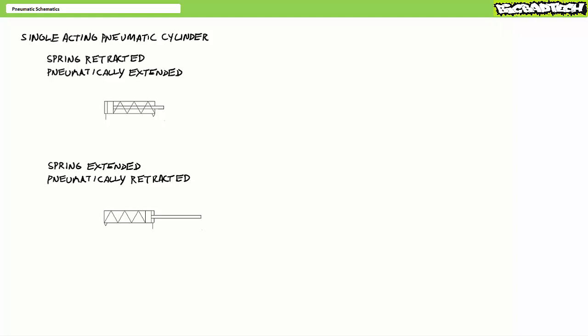Pneumatic cylinders convert pneumatic power to linear mechanical power. There are a dizzying array of special purpose cylinders, but most fall into two general classes, single acting and double acting. Single acting pneumatic cylinders have only one port and only actively perform one movement. Ordinarily, single acting pneumatic cylinders rely on a spring or the weight of a lifted object to passively perform the opposite movement.